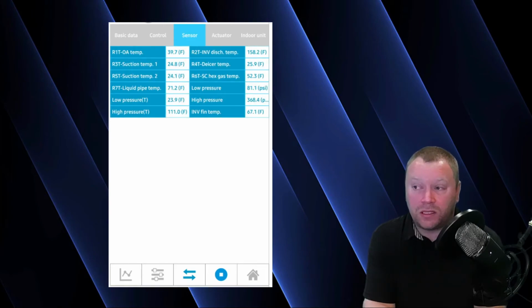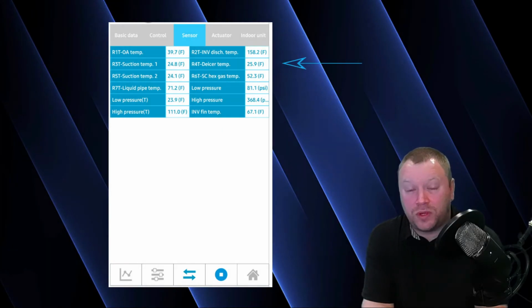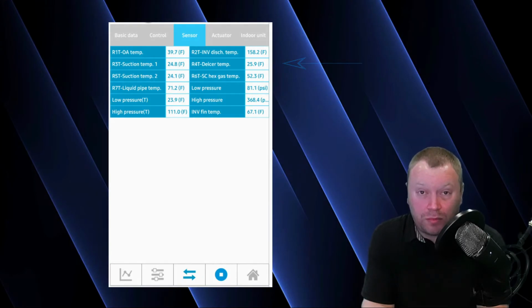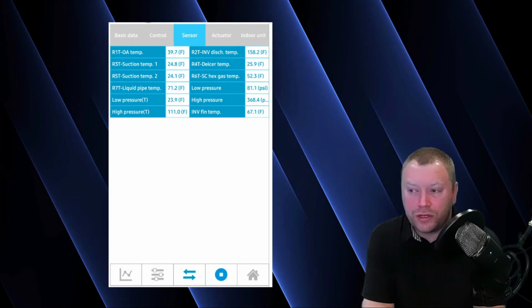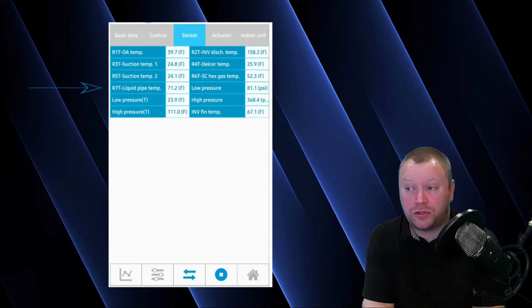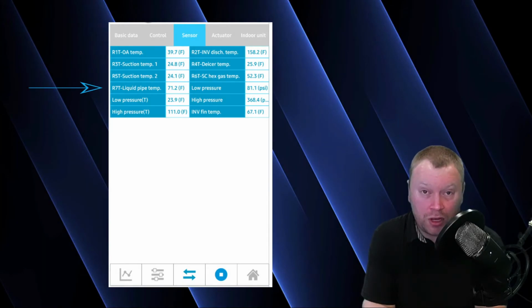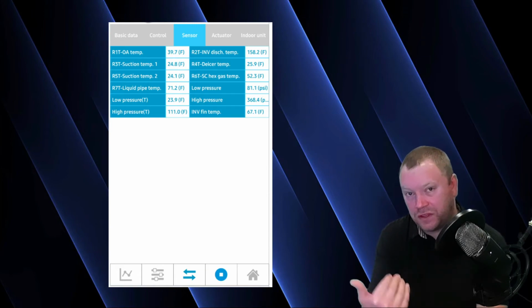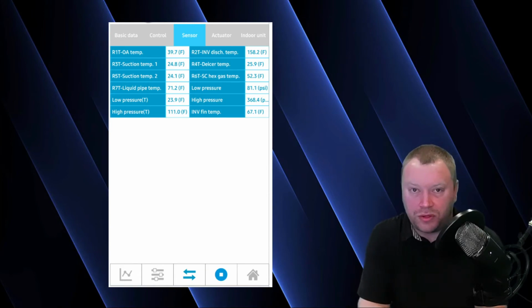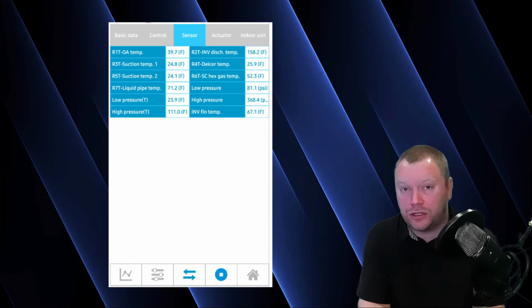So when I go back to my sensor data, I'm going to look at something called my de-icer temperature, which is the heat exchanger liquid pipe thermistor. Where you see R7T liquid pipe temperature, that's the actual liquid pipe temperature before it hits the electronic expansion valve. So on the field side at the outdoor unit, that's the combined liquid temperature of everything coming back to the outdoor unit. And then after it goes through the expansion valve, the de-icer temperature is the temperature of the liquid going into the heat exchanger.